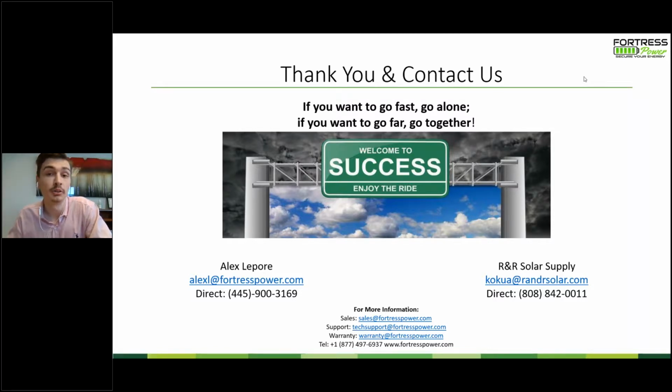All right, everybody, any other questions, anything else that I can go over? Jake brought up a really good point with how many eFlexes to the Solark you can set up in closed loop communication. He mentioned one eFlex with one Solark. That's not something I'd recommend because it's a pretty beefy inverter with a very small battery. You will be able to use one of the Solarks with two of the eFlexes in closed loop communication. And in that same capacity, you could use one of the Solarks with three of the eFlexes.